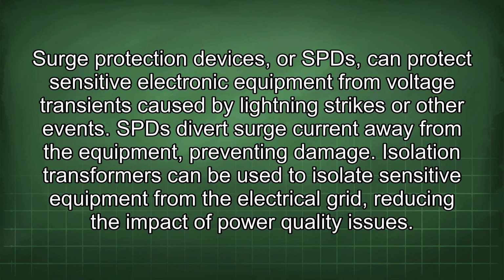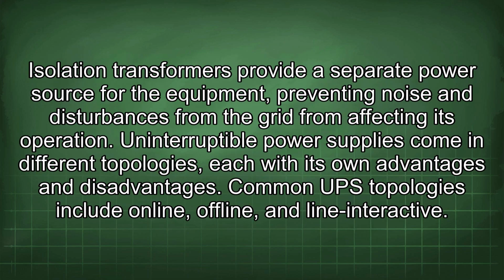Isolation transformers can be used to isolate sensitive equipment from the electrical grid, reducing the impact of power quality issues. Isolation transformers provide a separate power source for the equipment, preventing noise and disturbances from the grid from affecting its operation. Uninterruptible power supplies come in different topologies, each with its own advantages and disadvantages.